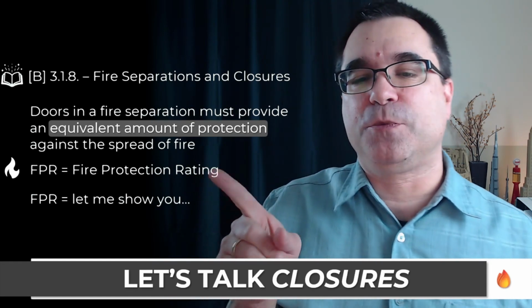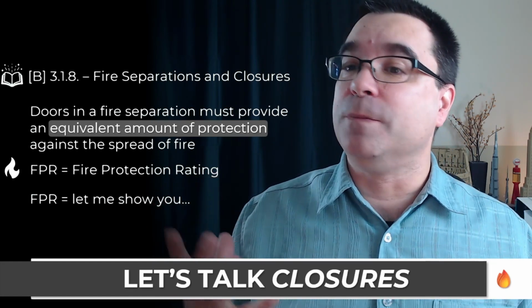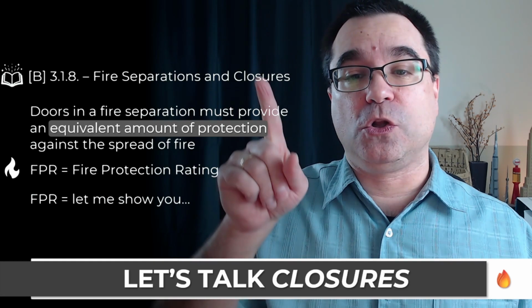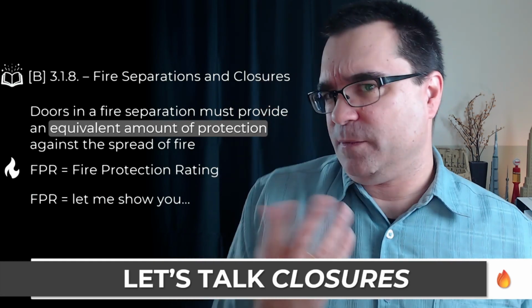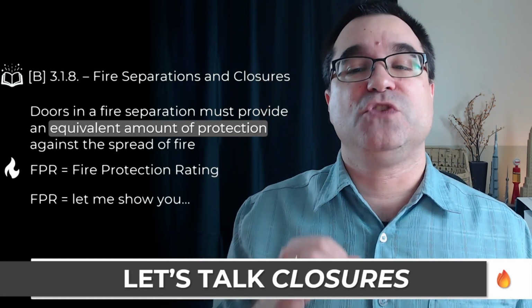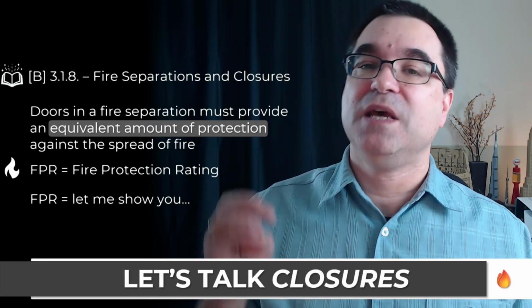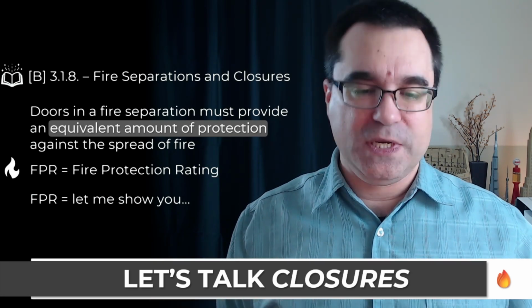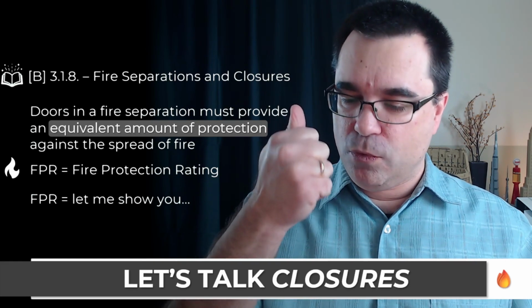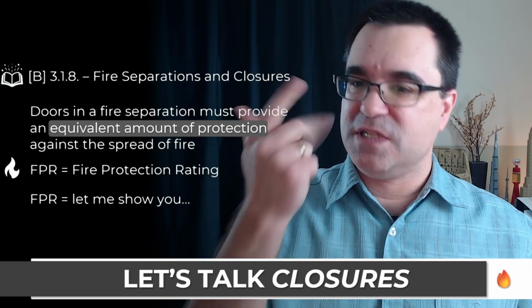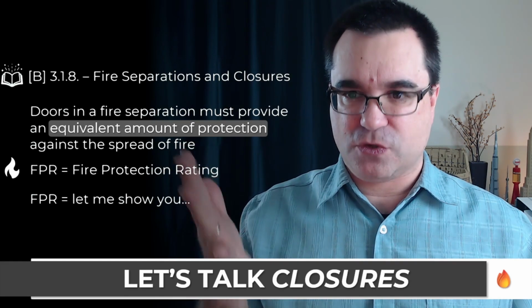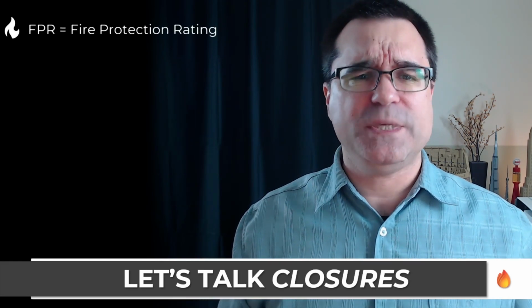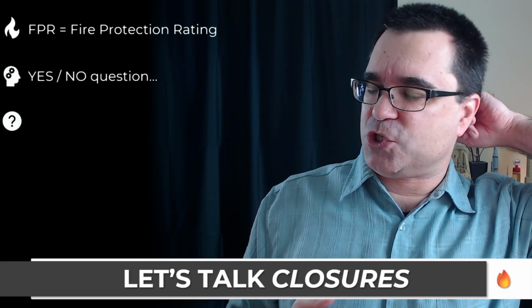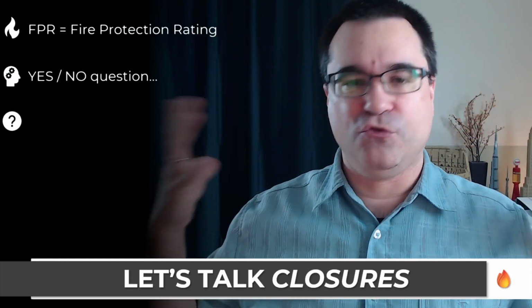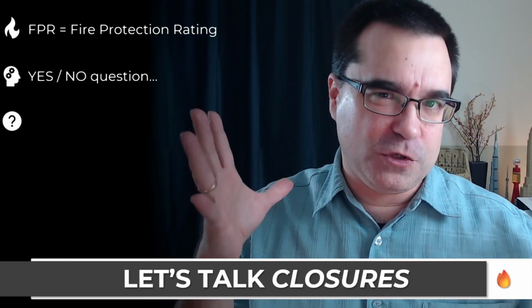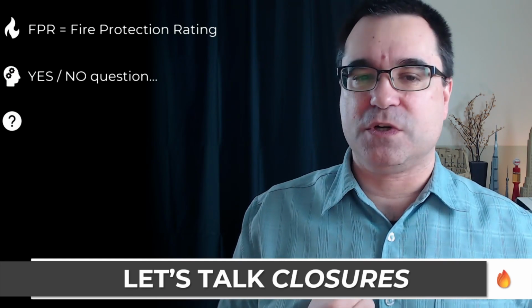So here's an interesting thing. As soon as you see fire protection rating in hours or minutes, you know it's related to closures. And for us, it's going to be mostly doors. Whereas if you see fire resistance ratings, you know it's related to fire separations like walls, floors, ceilings, roofs, that sort of thing. Okay? So let me show you a little bit about fire protection ratings and how they're determined for closures, for doors, okay? For us, it's doors.